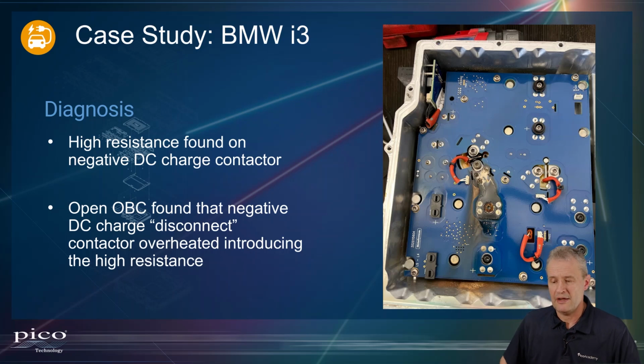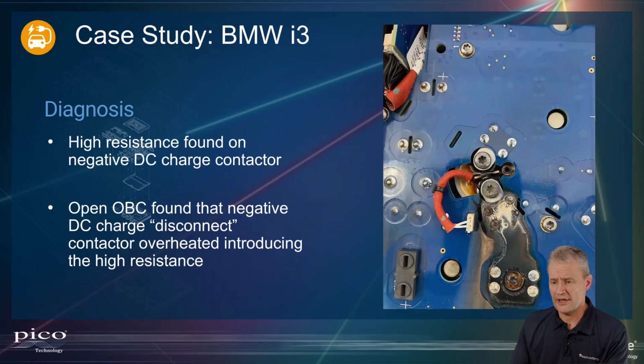So yeah, we saw with the BNC Plus resistance lead how we had a value, sometimes an open, sometimes an intermittent. But when we actually drill down to what we thought was the good contactor on the positive side, even that had an excessive milliohm resistance. So in that scenario, it's a no-go.